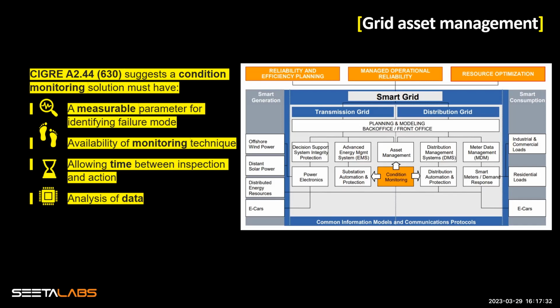I'll give you an interesting focal point here. My PhD was focused on moisture dynamics in power transformers. One of the challenges we face in moisture dynamic mathematical modeling is that moisture in the insulation paper of a transformer is very hard to monitor because the insulation paper is not easily accessible. So what do we do? We apply indirect methods such as mathematical models, mass conservation models, or equilibrium charts, in order to estimate what could be the moisture content in the paper.